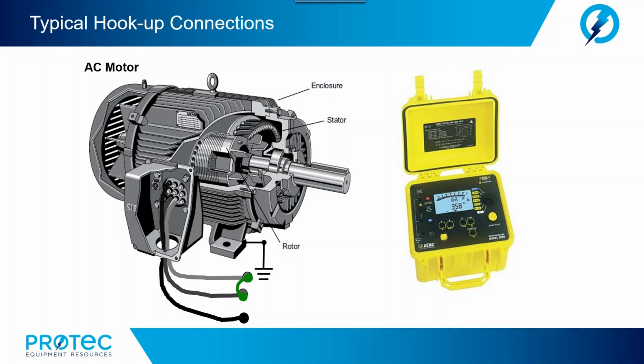The connection leads, bushing riggings, cables, switches, capacitors, surge arresters, voltage transformers, and other external equipment may greatly influence the insulation resistance reading. It is recommended that measurements of the insulation resistance be made with all external equipment disconnected and grounded. In all cases, a common ground should be used to avoid any undesirable effects on the test results due to stray losses in the ground circuit.